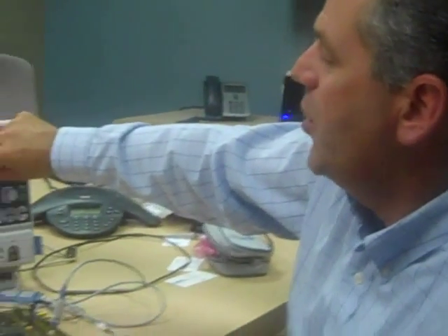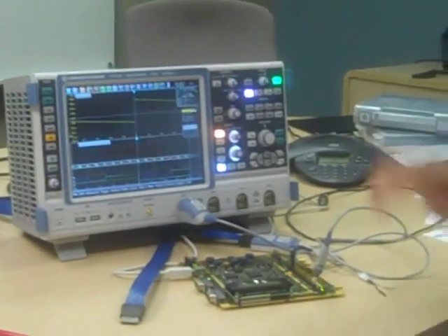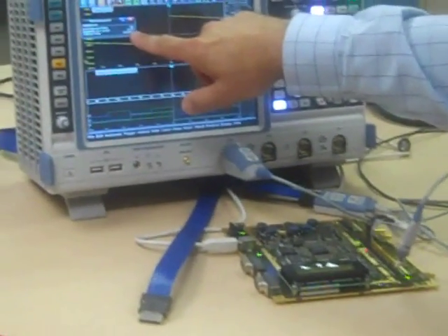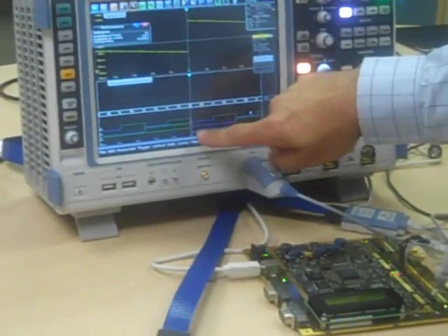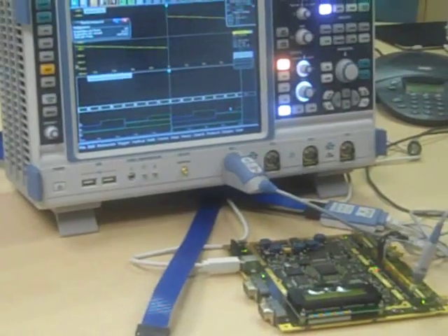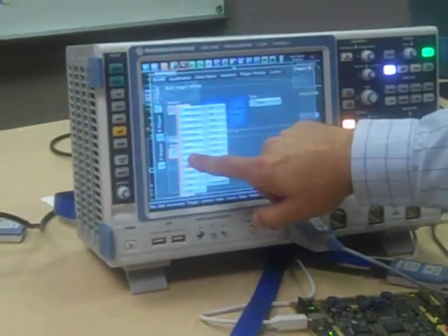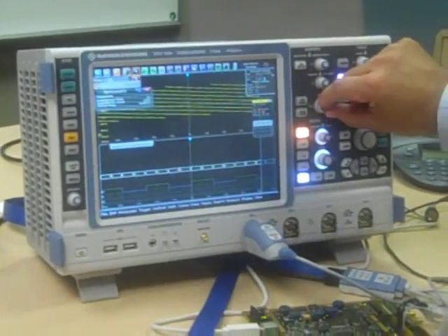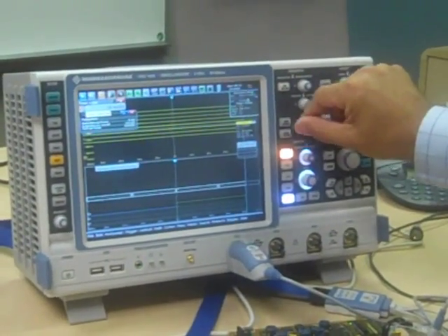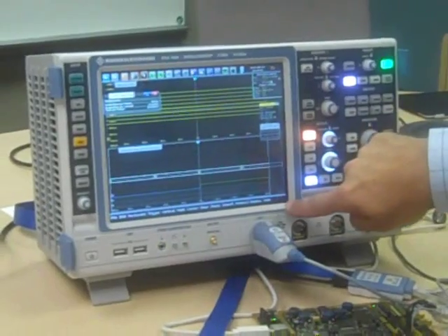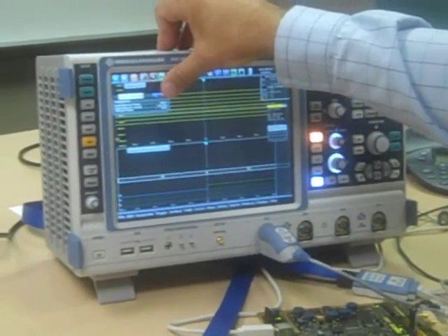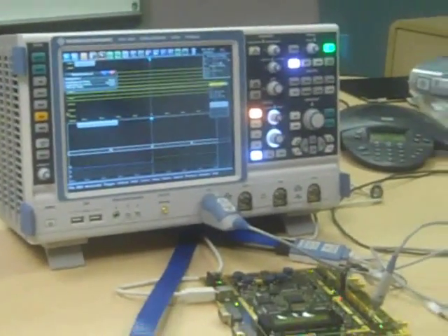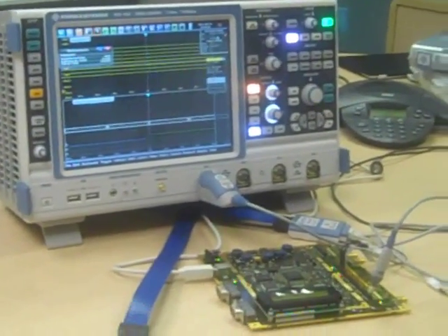In addition to the oversampling and deep memory, the instrument also features very high update rate in the MSO mode. The MSO mode will update at 200,000 waveforms per second. I'm going to turn on our performance measurement, and here we can see the readout as waveforms per second. I'm going to change the trigger to the least significant bit, which is the one that toggles the fastest, and adjust my time scale. Now we're triggering on the least significant bit with a 1,000 point record, and you can see the update rate is about 195,000 waveforms per second for all 16 logic channels sampled at the same time as all four analog channels.